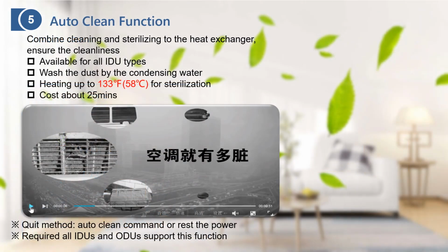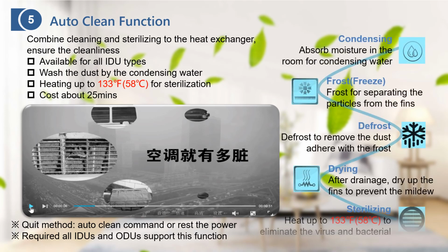Auto clean. It is a new function. The purpose of this one is just to clean and sterilize the indoor heat exchanger. How to achieve it is, first we will make it to be condensing, which is to absorb the moisture in the room for condensing water. And then we make this water become ice, which is frost. And then to defrost, which is to clean the indoor heat exchanger. Then we need to heat up, which is to dry the water. And the last is to heat up to 58 degrees to eliminate the virus and the bacteria.